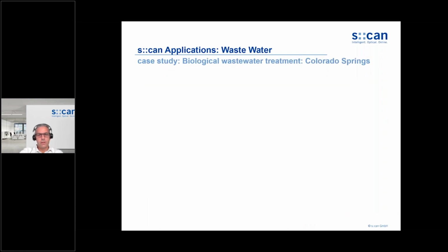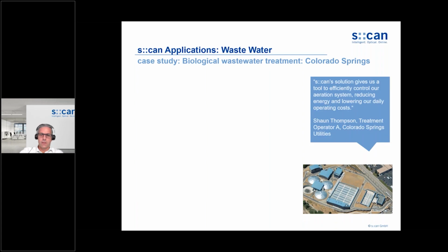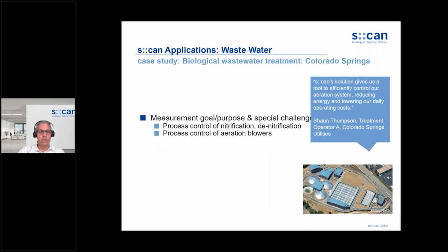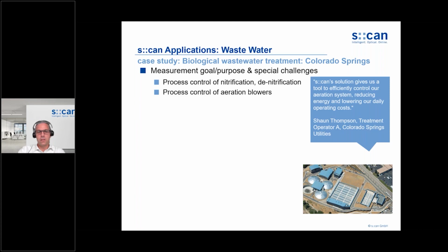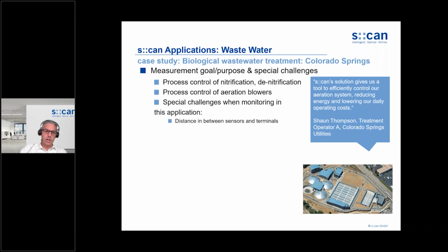A case study in this respect is a wastewater utility in Colorado Springs. As you can see here, the operators are pretty happy with our solution, and they even mentioned that they were able to lower the daily operational costs by means of our products. What are the goals in this case study? To process control nitrification and denitrification and the aeration blowers. Special challenges when monitoring this application was the distance between the sensors and terminals. Based on the design of the plant, there was a big distance between the terminals and the sensors, and we had to overcome this.